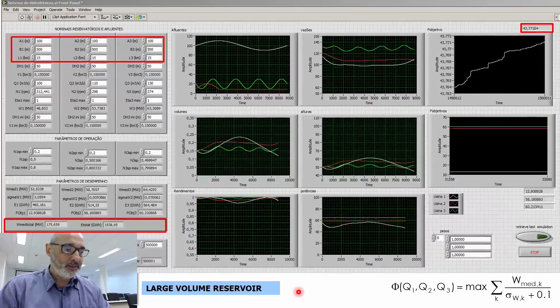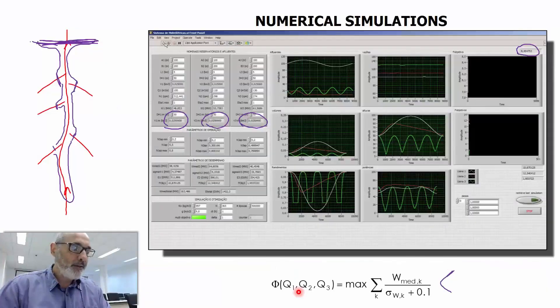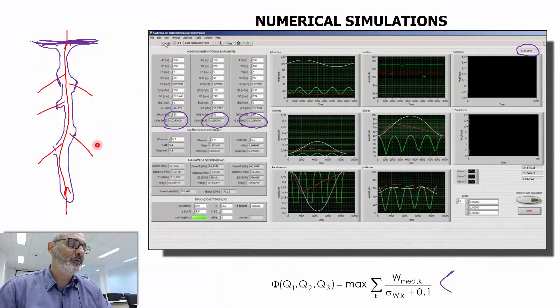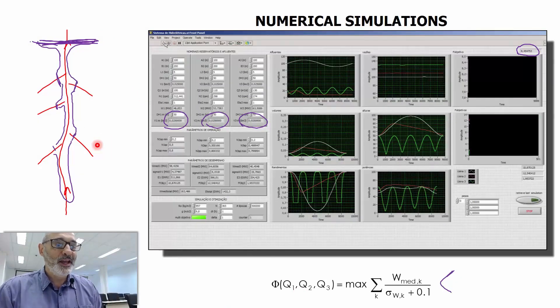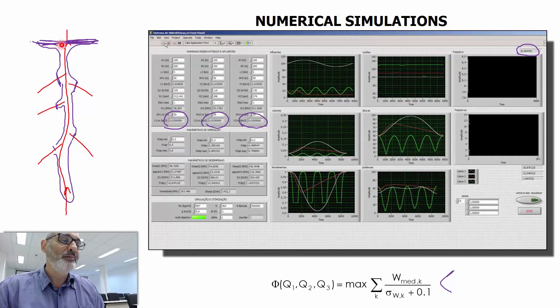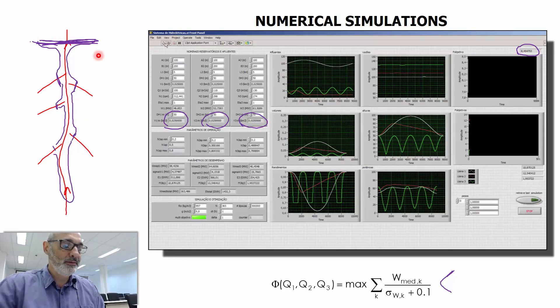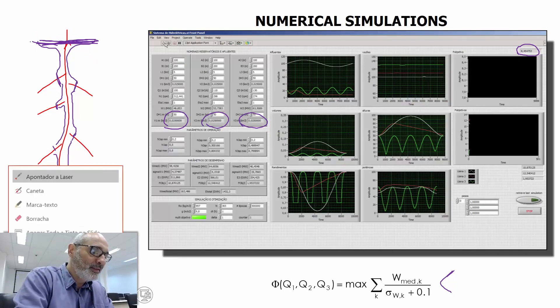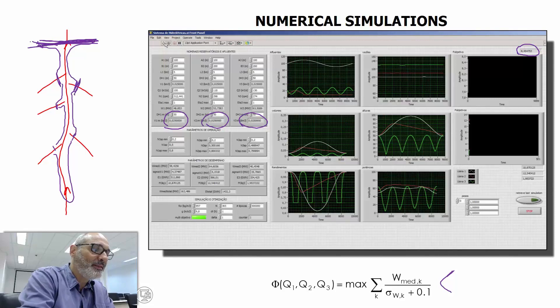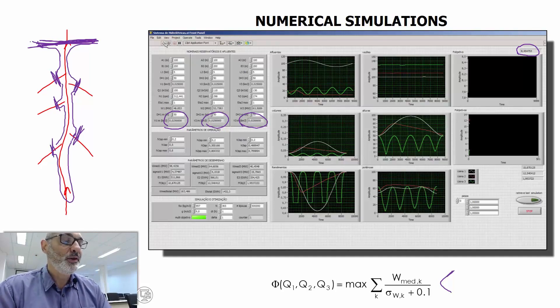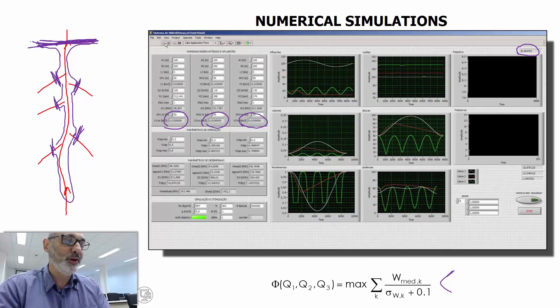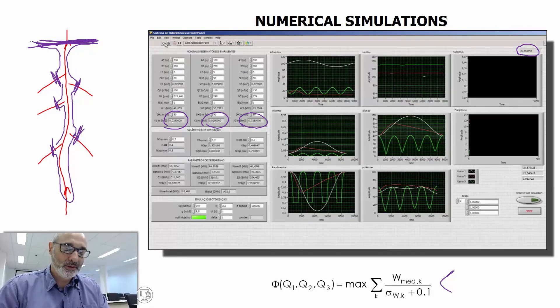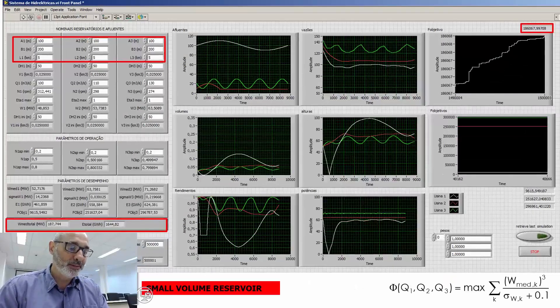By reducing the reservoir size in Belo Monte, if you make the proper calculations, you might conclude it would be better not to construct the reservoir at all. Having multiple smaller reservoirs requires more civil engineering structures and more concrete — which is great for concrete suppliers — but for electricity generation, it's not good. That's my point regarding Belo Monte.